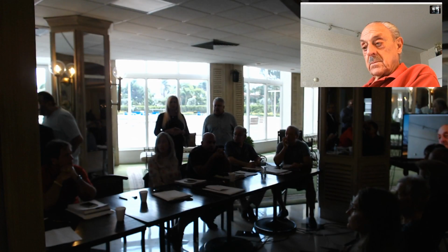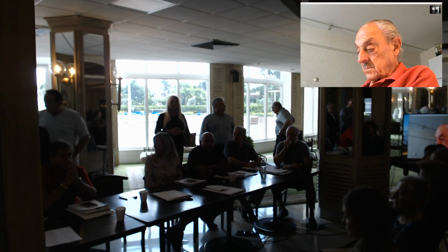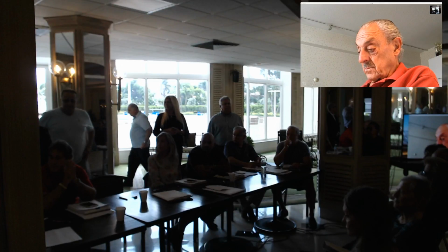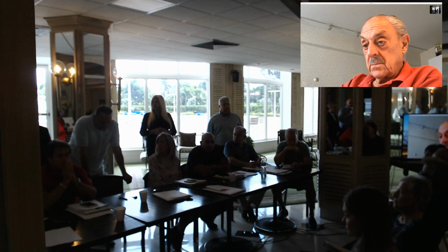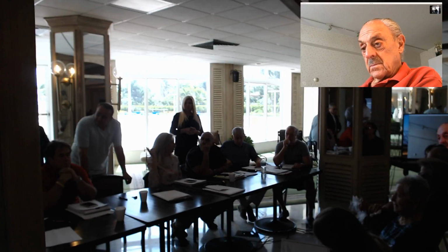At the beginning of the presentation, humidity was named the most important issue in the building, and it's the first item the board insisted we deal with. Over the years, this building had no dehumidification because the steam boiler was never up and running, so any humidity issues were compounded. With the board's help, we got the steam boiler running as a temporary solution until the mechanical rooms are completed. The intent is to control the building overall, removing the biggest problem, which is the lack of dehumidification.